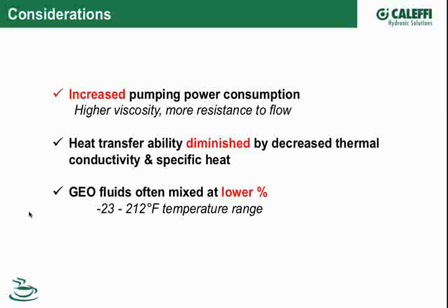Yeah, but I think you have to be careful. I wouldn't agree with this 23 degree. I think that's a little too weak a concentration. And one of the problems that you have with glycols at the weak concentration is they're very biodegradable. And if you get too weak, you're going to have your fluid biodegrading in your system, which is not a good thing. As you get up in concentration, 20 to 25% or more, so you're going to be in the 18F or lower freeze point, then there's too much glycol in there. It basically imparts osmotic pressure, which dehydrates cell tissue.